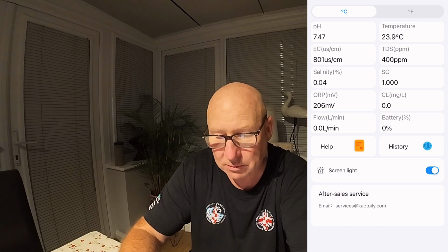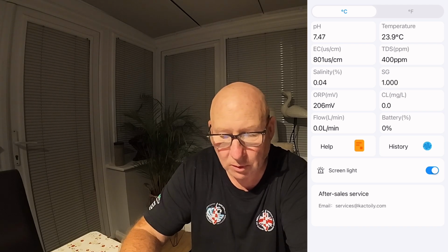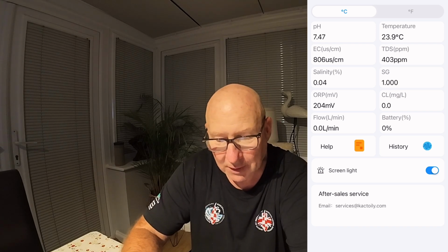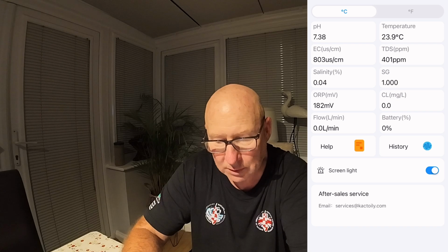CL, which I take is chlorine - I'm not 100% sure, but pretty sure. It's showing 0.0 for chlorine, and battery is 0% because there's no battery power, it's direct. So that's 1, 2, 3, 4, 5, 6, 7 - the CL isn't one you use then. So you've got pH, EC, salinity, ORP, temperature, TDS, and specific gravity.